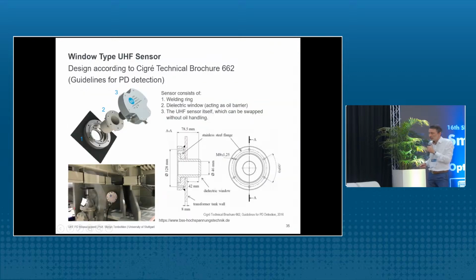The others are so-called window type sensors. These are welded on the tank wall. We have here a dielectric window, and here is the sensor itself. The design of these sensors is more or less standardized also in a Cigré brochure. So such a sensor looks like this. Of course, these sensors can only be installed in the factory, because you have to weld something on the tank wall. So this is the typical technology for new transformers.